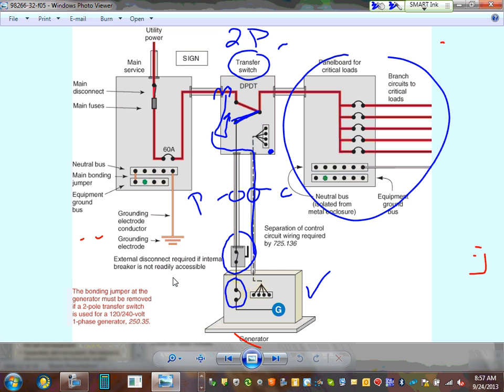In this case, you can have a two-pole or three-pole circuit breaker. You have the options. If it's called a separately derived system, and we'll talk about separately derived systems when we go to commercial, guys, the only difference is that you switch the neutral. Do you switch the neutral? Yep, separately derived system.